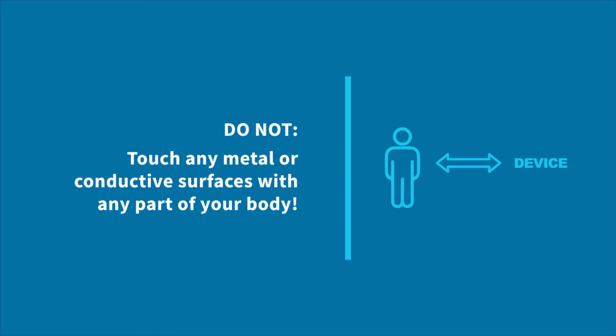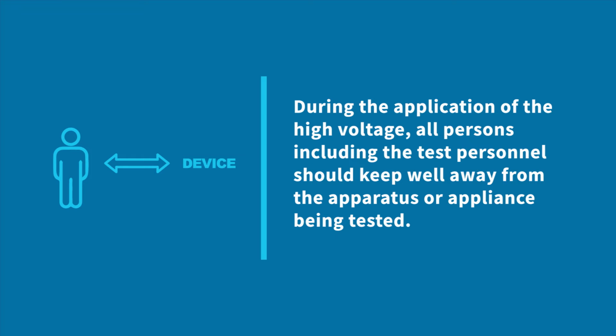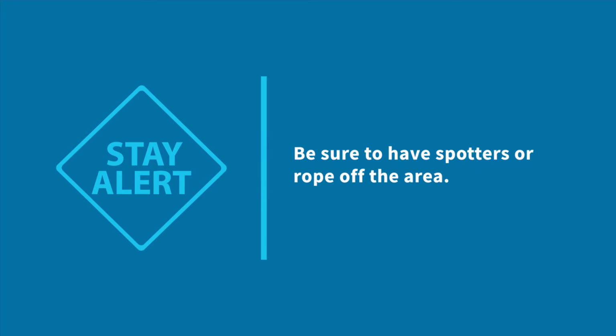Do not touch any metal or conductive surfaces with any part of your body, and ensure no other persons or equipment are exposed to the conductive surface during the test. During the application of the high voltage, all persons, including the test personnel, should keep well away from the apparatus or appliance being tested. Be sure to have spotters or rope off the area.